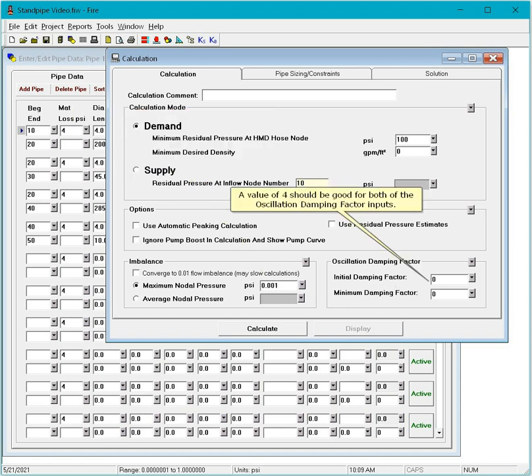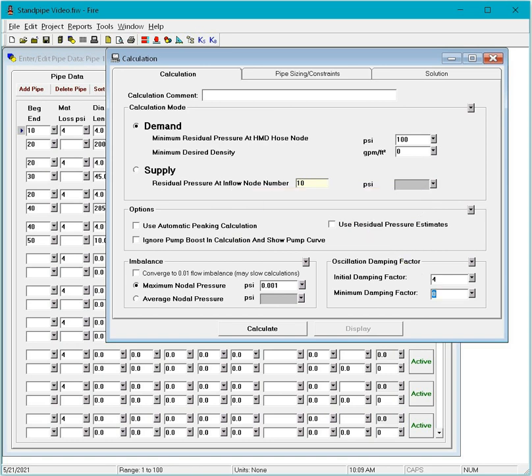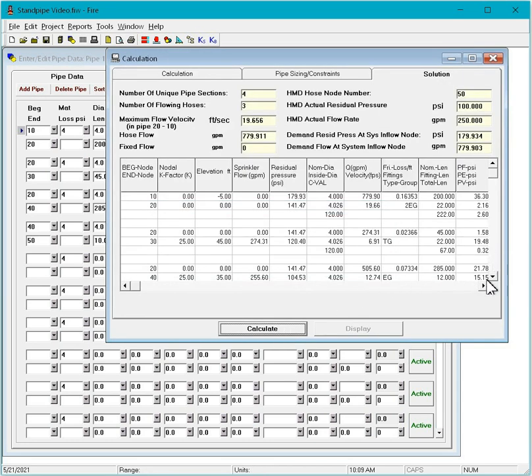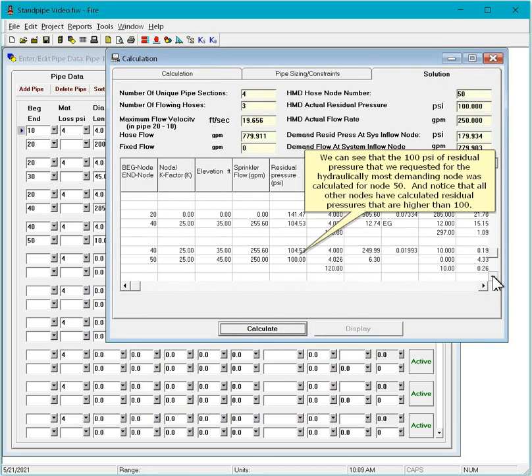A value of 4 should be good for both of the oscillation damping factor inputs. Click the calculate button. We can see that the 100 PSI of residual pressure that we requested for the hydraulically most demanding node was calculated for node 50. And notice that all other nodes have calculated residual pressures that are higher than 100.